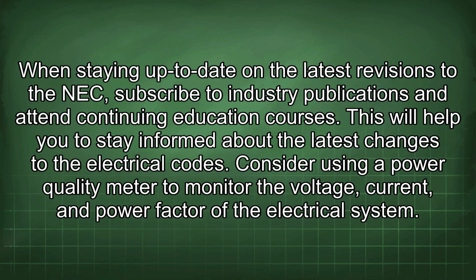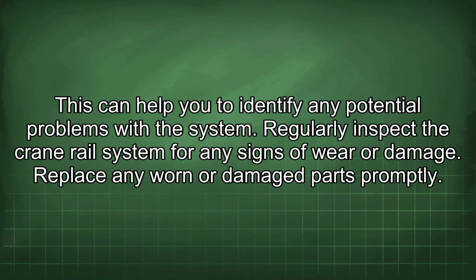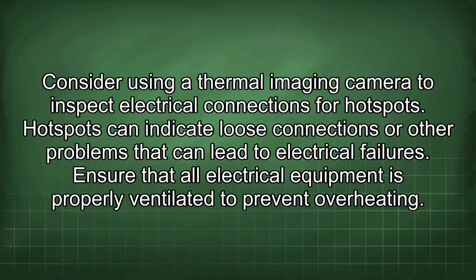Consider using a power quality meter to monitor the voltage, current, and power factor of the electrical system. This can help you to identify any potential problems with the system. Regularly inspect the crane rail system for any signs of wear or damage. Replace any worn or damaged parts promptly. Consider using a thermal imaging camera to inspect electrical connections for hotspots. Hotspots can indicate loose connections or other problems that can lead to electrical failures.